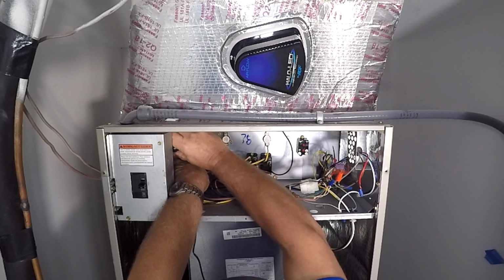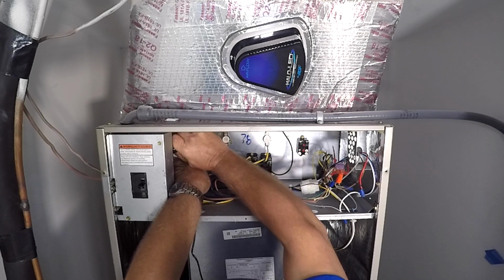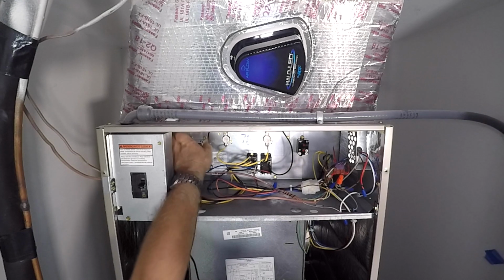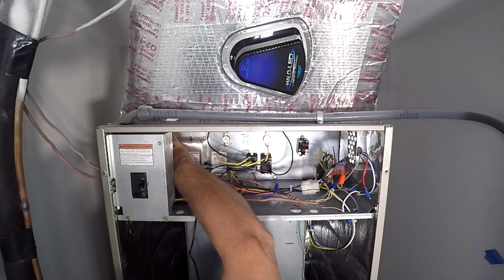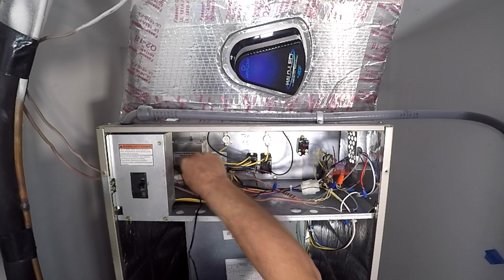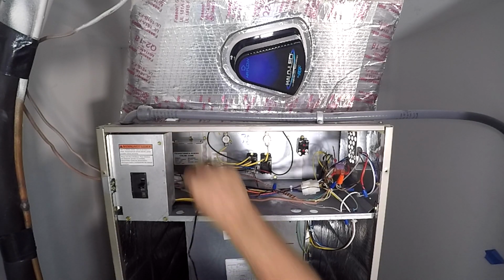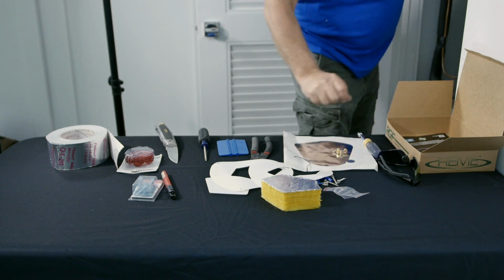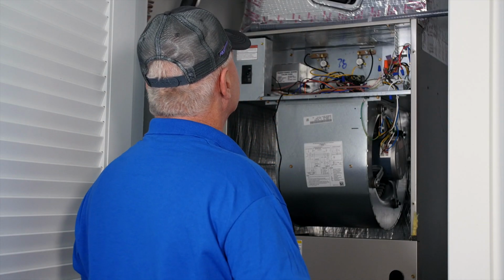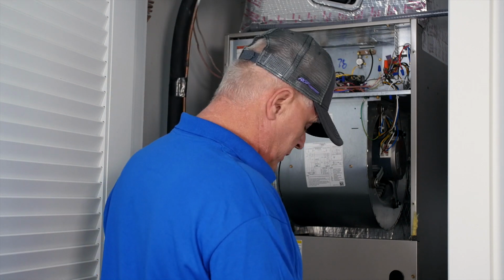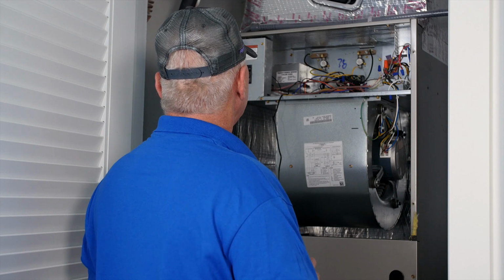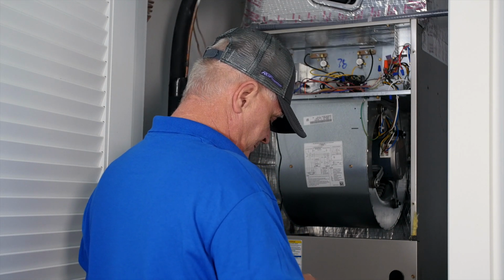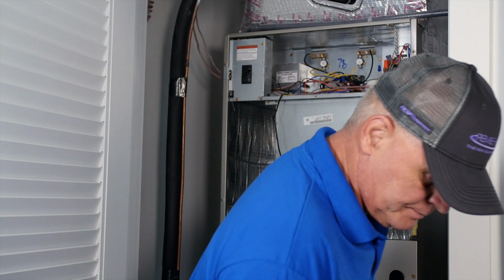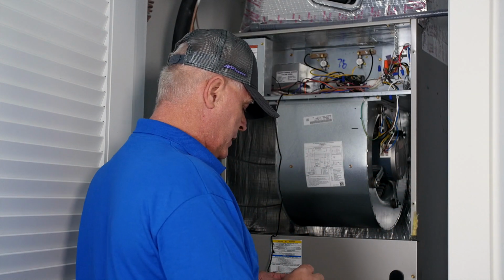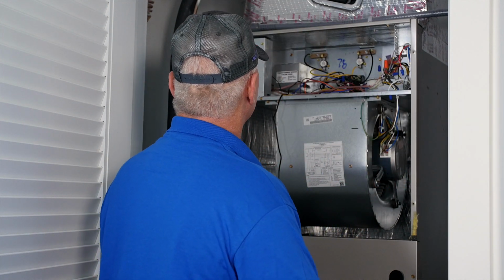Especially if you do not get a solid connection of the unit and it is loose in here, you definitely want to install it in a different manner, meaning drilling a few holes in it. We're going to have to add a little wiring here as our unit is not quite close enough to connect all of the wires together, so we're going to make a few jumpers for this. It does not take a very heavy gauge wire for this. I am using 16 gauge wire for what I'm going to be doing here.